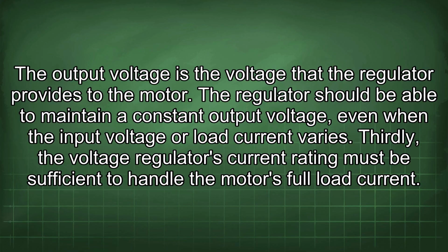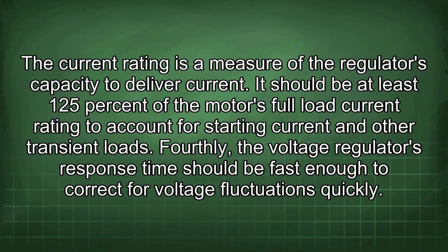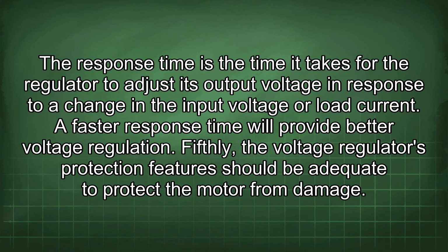Thirdly, the voltage regulator's current rating must be sufficient to handle the motor's full load current. The current rating is a measure of the regulator's capacity to deliver current. It should be at least 125% of the motor's full load current rating to account for starting current and other transient loads. Fourthly, the voltage regulator's response time should be fast enough to correct for voltage fluctuations quickly. The response time is the time it takes for the regulator to adjust its output voltage in response to a change in the input voltage or load current. A faster response time will provide better voltage regulation.